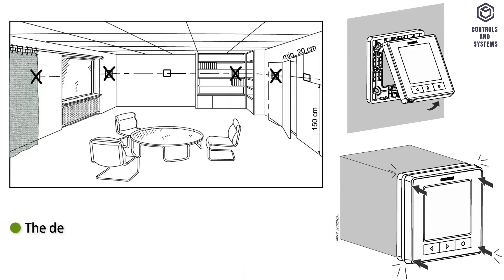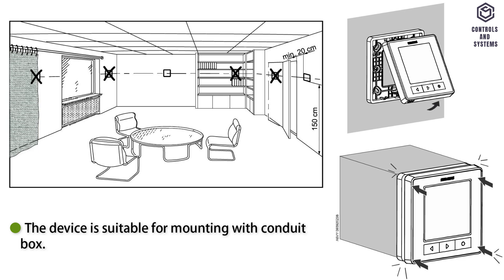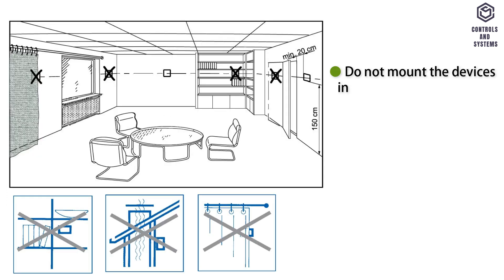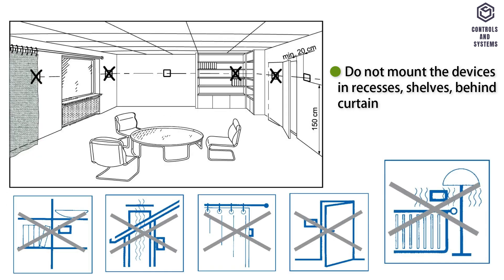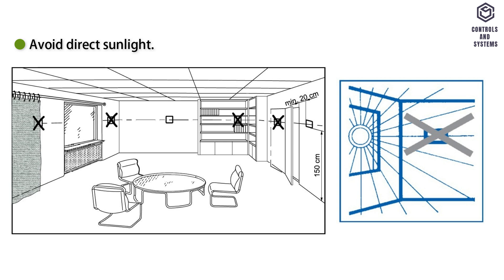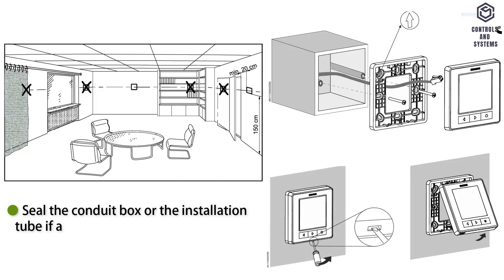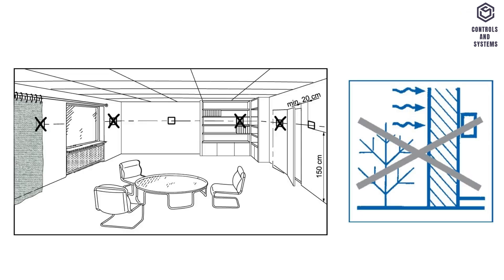Mounting: the device is suitable for mounting with a conduit box. Recommended height is 1.50 meters above the floor. Do not mount the devices in recesses, shelves, behind curtains or doors, or above or near heat sources. Avoid direct sunlight. Seal the conduit box or the installation tube if any, as air currents can affect sensor readings. Adhere to allowable ambient conditions.